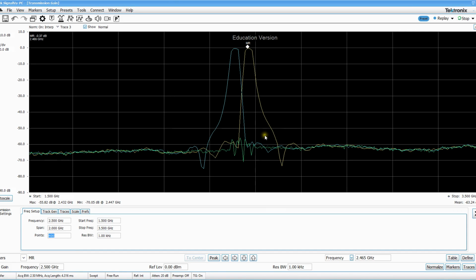Now, one thing this tracking generator doesn't have, or at least I couldn't figure out how to do, is that you cannot set the tracking generator step to 0. So you can't do a 0 span. Normally a 0 span is useful because that would allow you to use your tracking generator as a standalone synthesizer when you don't have it in any circuit like this. But I cannot figure out how to do this. I don't think it's capable of doing that.